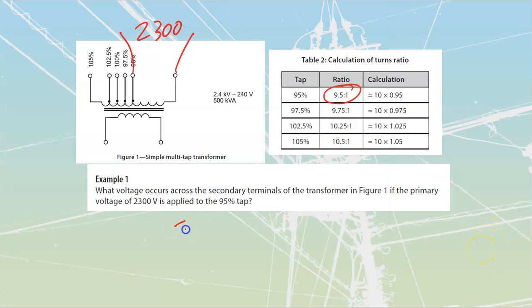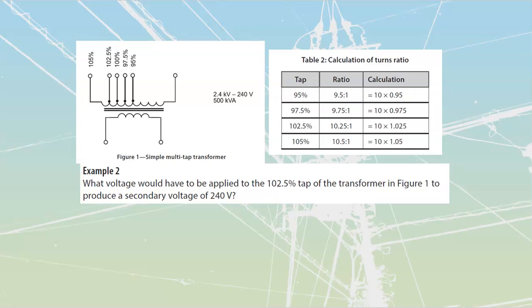Slightly different calculation method than what they go through. They've got more math written out, but this is just as correct. What's our voltage? And then if I know what my ratio is, this one should be 9.5 times smaller over here. Example number 2: what voltage would I need to apply to the 102.5% tap of the transformer in order to produce a secondary voltage of 240? This is a backwards type of question because we don't pick the voltage. We have a voltage. There's line drop that has already happened and has brought us to this point. But we can humor them and work through this thing backwards.